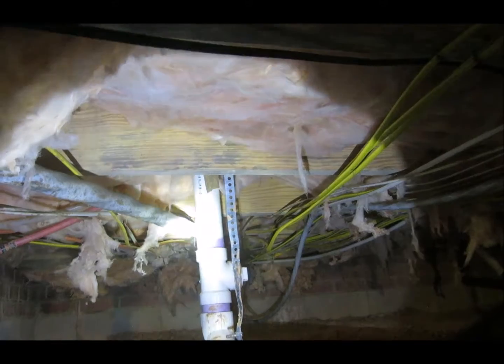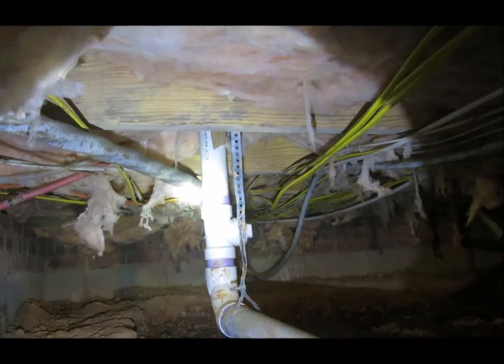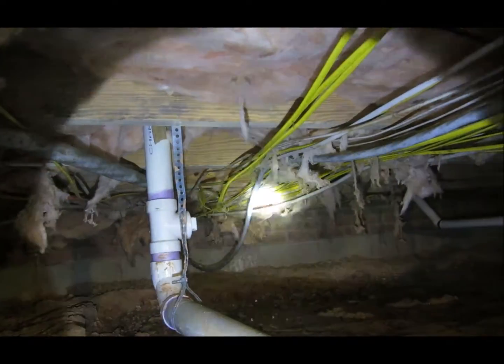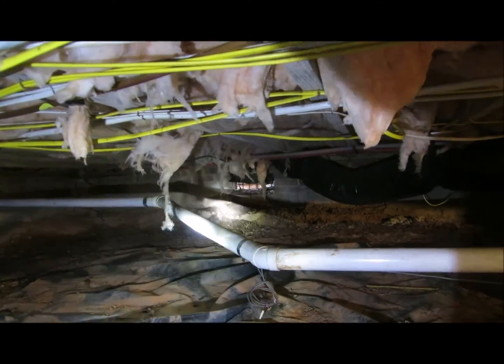Here's mold extensively on the incoming electrical wires. This area has been excavated, and you can see the discoloration in the soil. It's wetter, and then the flooding that has occurred on the moisture barrier. Very low, difficult in here to work. And there, a bunch of debris coming in the foundation vent.